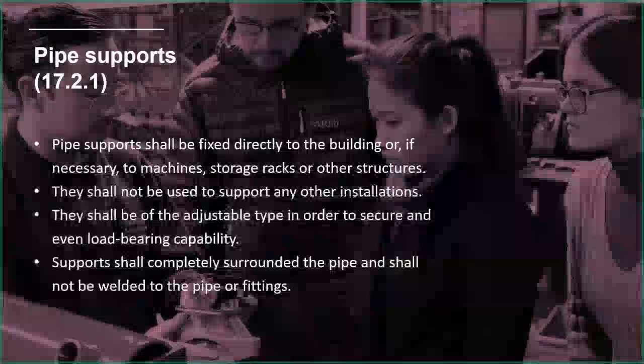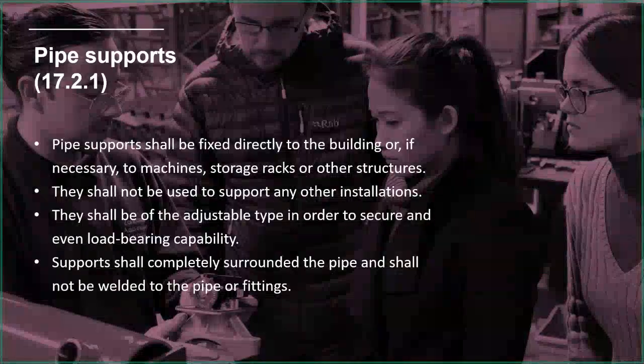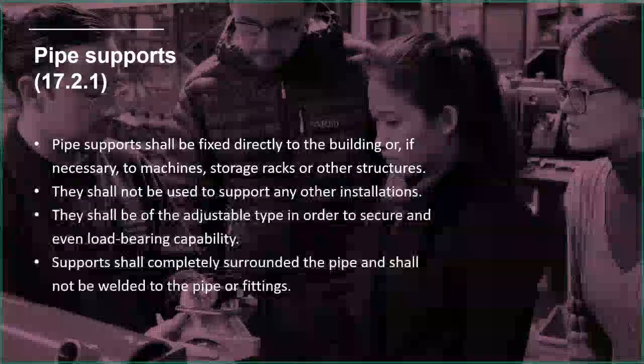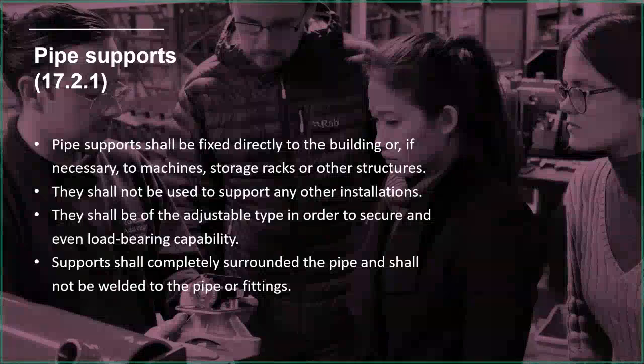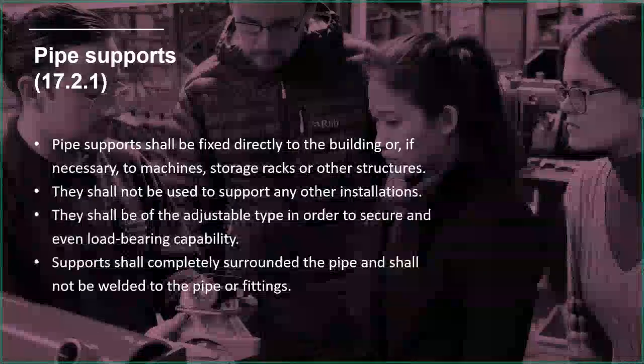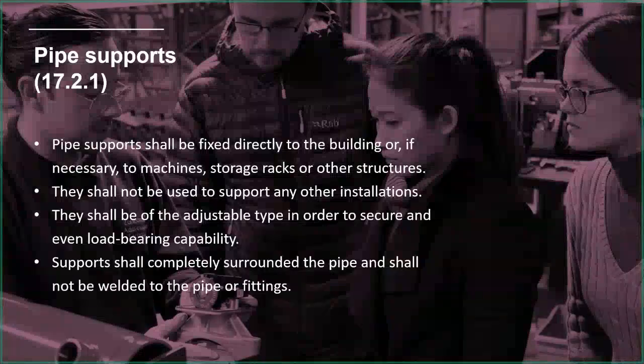The support shall completely surround the pipe and shall not be welded to the pipe or fittings. There are different types of hangers and brackets, but all the types we use completely surround the pipe, so it can't jump off and come loose.